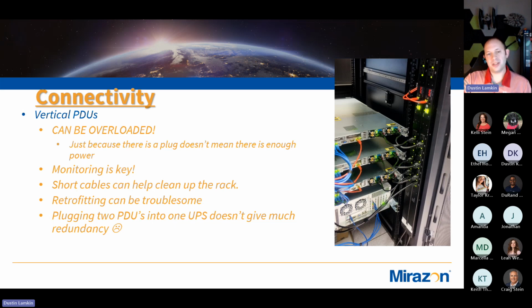That way you don't have to swap it out later, it helps so much. And the last piece is, if we have 2 PDUs but only one UPS, we still have that single point of failure of a single UPS. So that's something to think about. It still happens a lot, buying 2 UPSs to right size your systems can be hard, so that's something we need to think about.